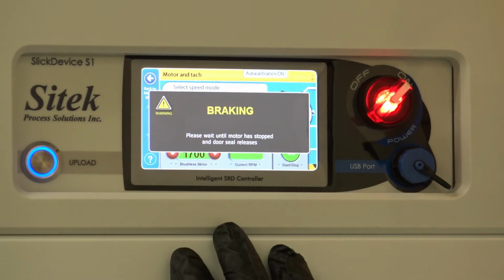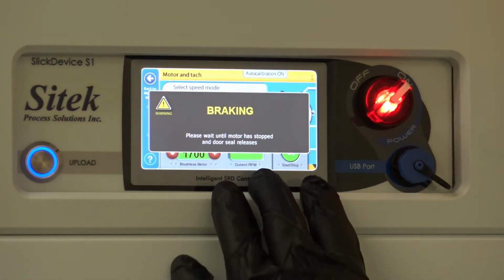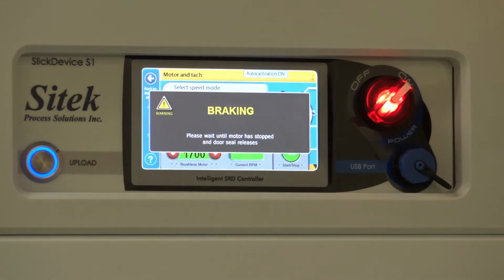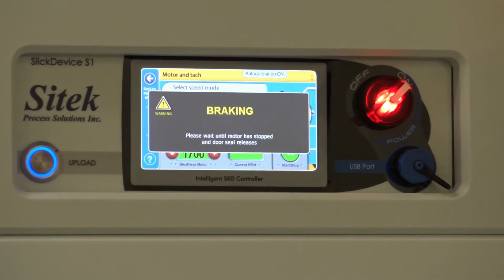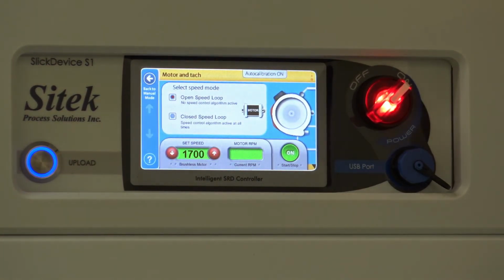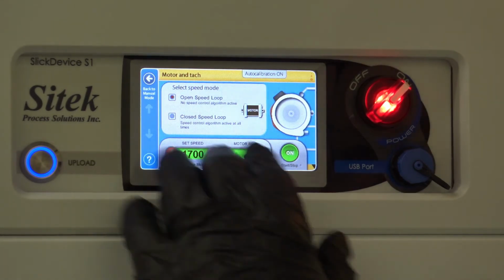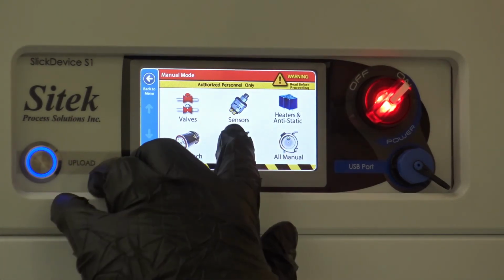And it's braking. It's giving you a warning, do not open the door until the motor stopped and the door releases. What happened is whenever you run this process, it's a safety feature, the door automatically locks. So don't do this if you have the door open and want to run the tool with the door open, because the seal is going to try to inflate and it's going to pop out of the door seal. That's a safety factor.